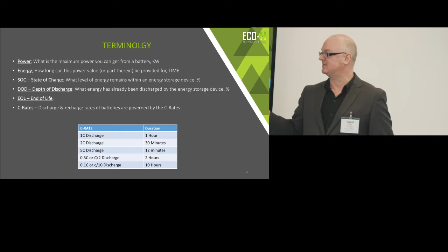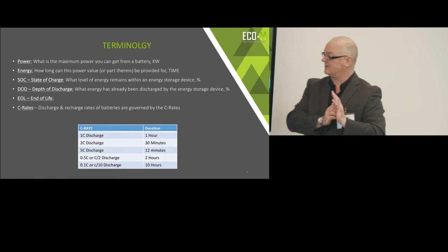So if you have a battery system or energy storage device with 1 megawatt hour, you discharge 1 megawatt for 1 hour. If it's got a 1C recharge rate, then you can throw 1 megawatt back into it, and in 1 hour it's recharged - again, very simple math. If it's got a 2C charge rate, then you can discharge by 1 megawatt, and you can throw 2C, or twice that power, back into it, so you can recharge in half the time.